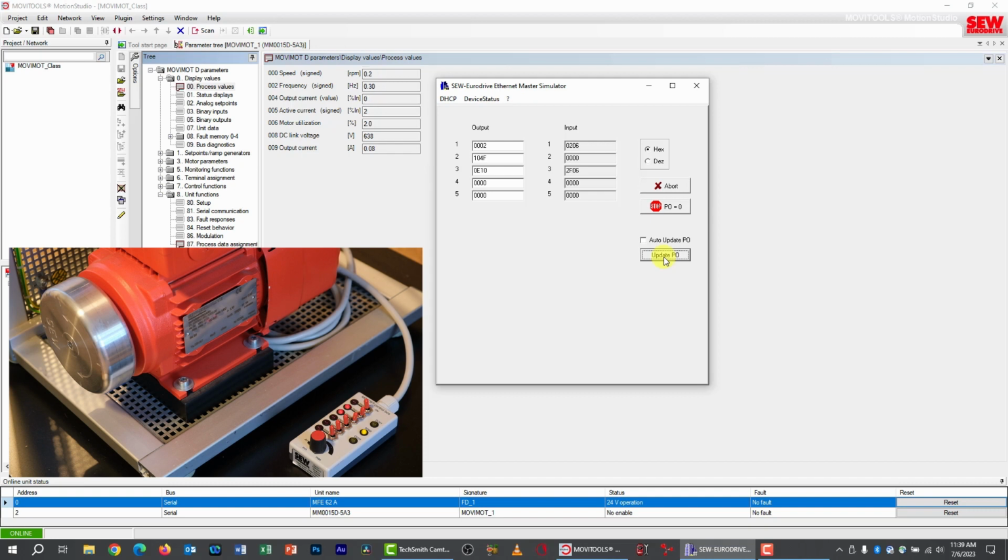All right, yes, I think that definitely worked. It came to a stop in about 2 seconds, and the brakes set at the very end. Let me write down our PIs again. We're going to interpret those to see what they're telling us a little later. And now we're going to run our drive in the counterclockwise direction to make sure it works, and we're also going to see if it takes 5 seconds to accelerate. We didn't notice that when we tested it a minute ago because we were busy worrying about that parameter that was messing us up. So let's change this to a 6 again to tell it to run.